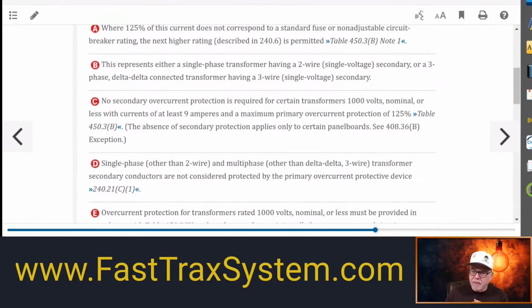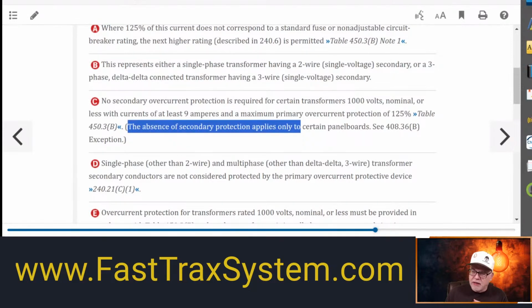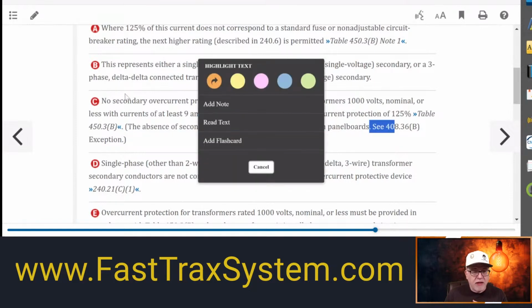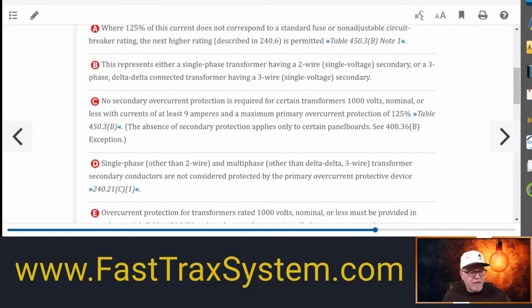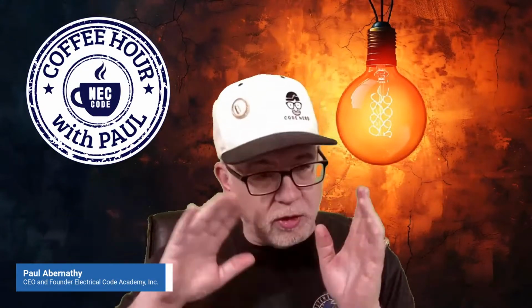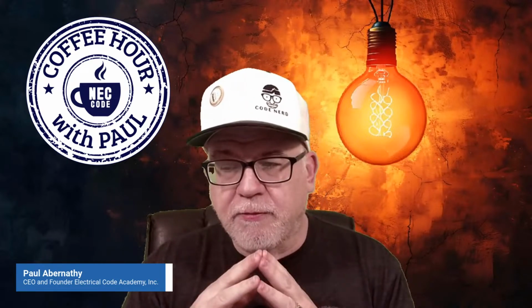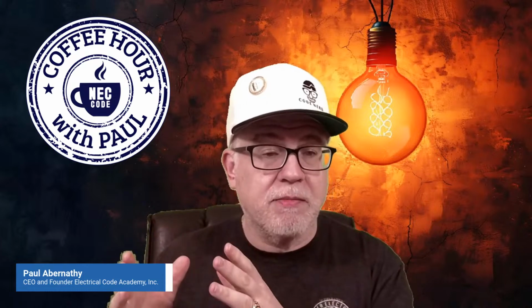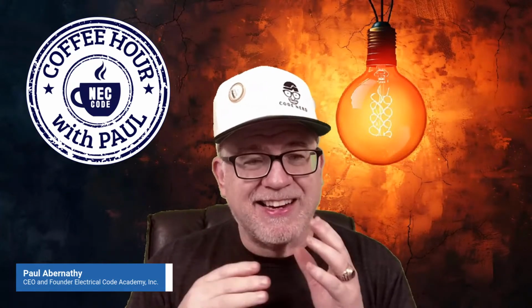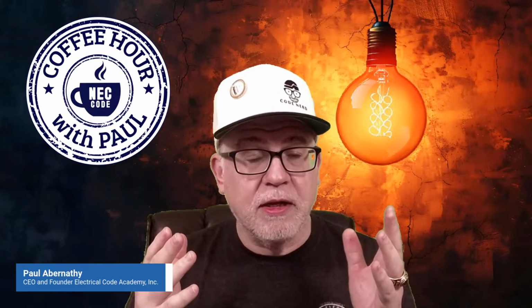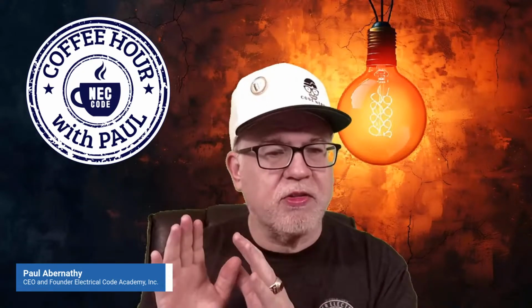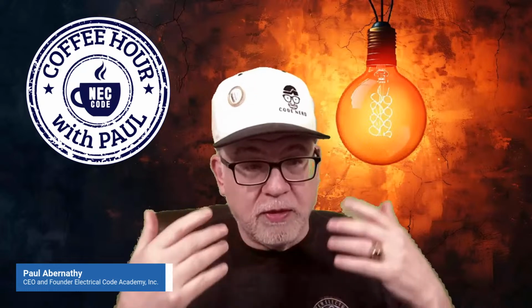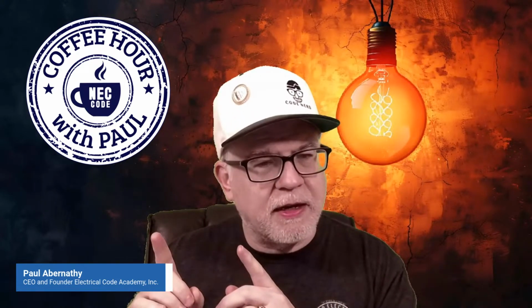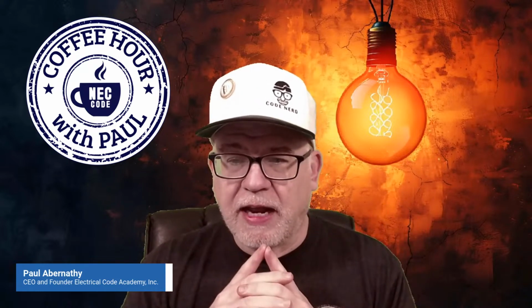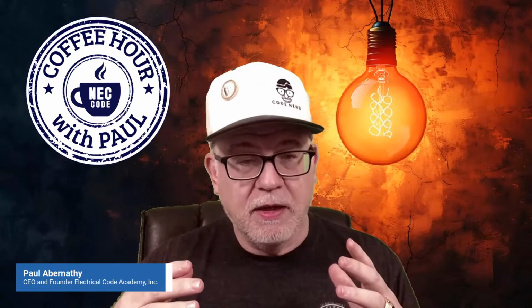Okay. Now, important note here, it says the absence of secondary protection applies only to certain types of applications in the panelboards and exceptions. Typically, anytime you have a panelboard, for the most part, when you have a transformer and you're feeding a panel on the secondary side, although we weren't going to talk secondary, if you do, then you're required by 408.36 to provide protection for that panelboard. That's going to pretty much dictate a lot of your secondary conductor sizing. Obviously, they have to handle the load, but at the end of the day, one question I get from people, and I only want to touch on this, is in this same transformer we've been discussing, a 75 kVA, if the secondary is not required to have any protection, then you have to make sure everything is protected from the primary.